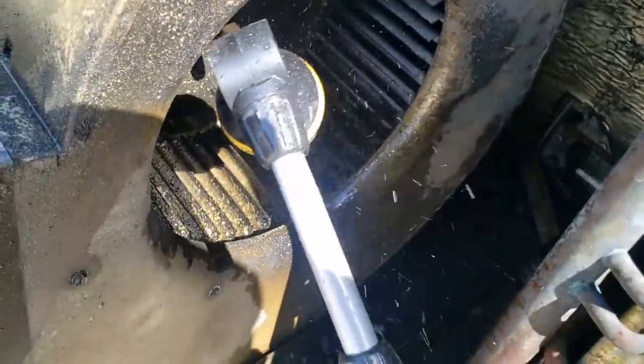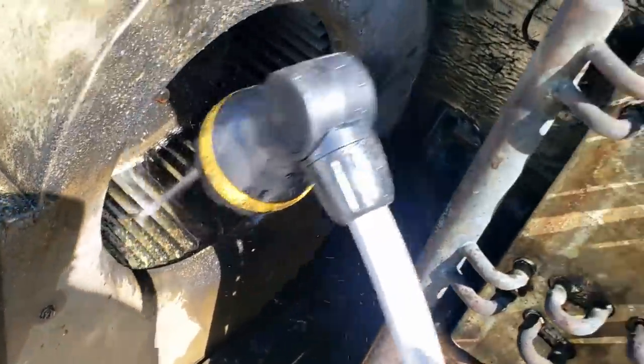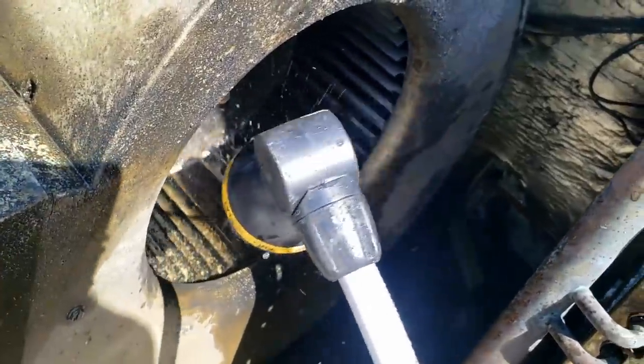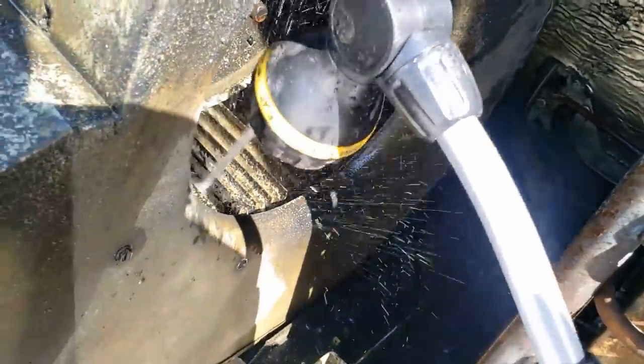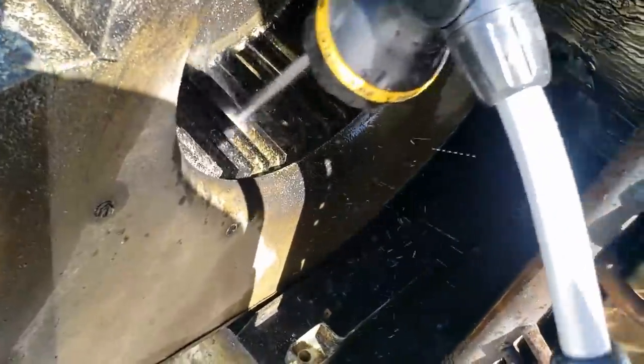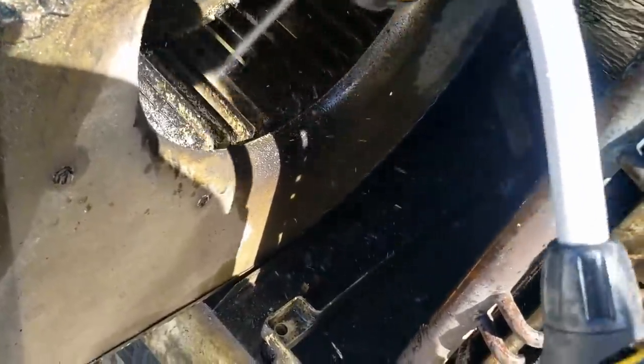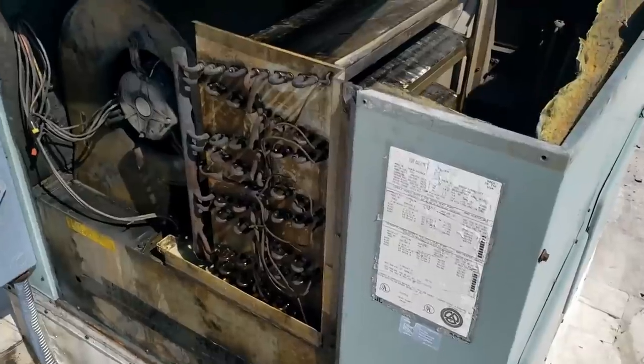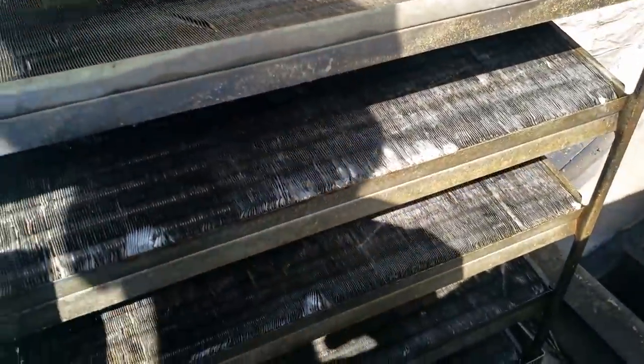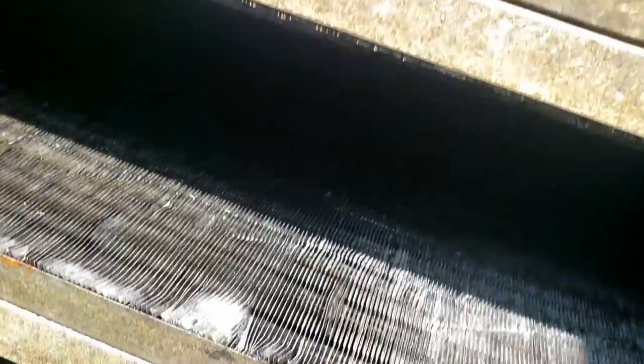We're just washing it — you can see the water coming right off the front here. It's getting a lot of it out. You don't want it to spin or it'll leap around and fall down on the motor. A little splash on the motor isn't going to hurt anything. We've got it cleaned out — coils look a lot better than they did.